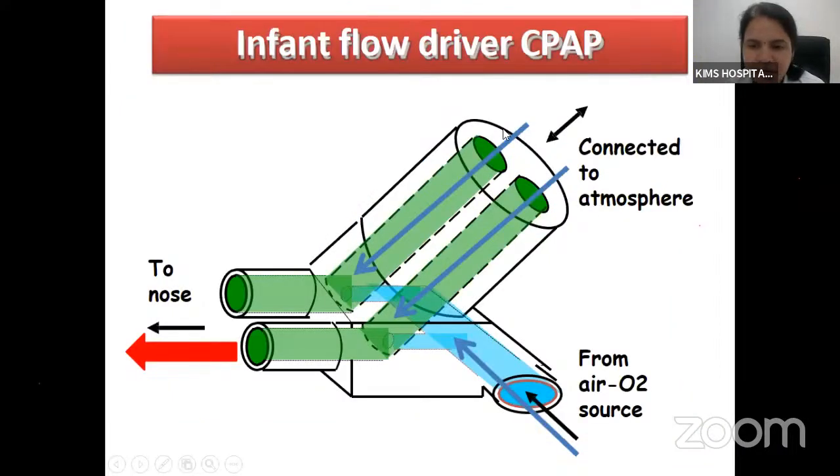So typically with the infant flow driver CPAP, as represented in this figure, we have the nasal interface here, which is usually in the form of a short binasal prong that is connected to the patient. And we have an inspiratory circuit exactly like we have with the bubble CPAP circuit that is connected to the blended source of air and oxygen.